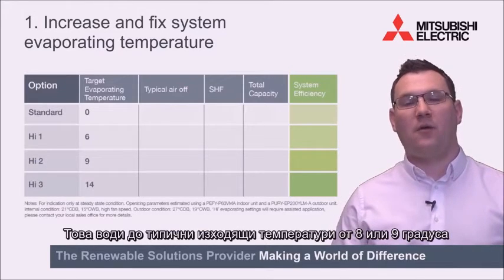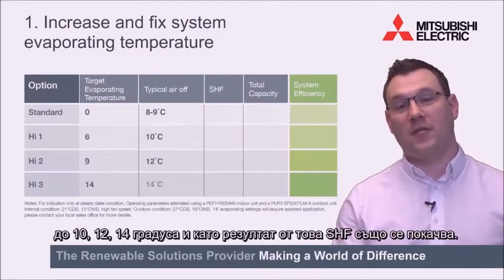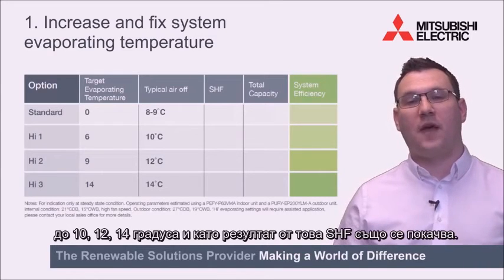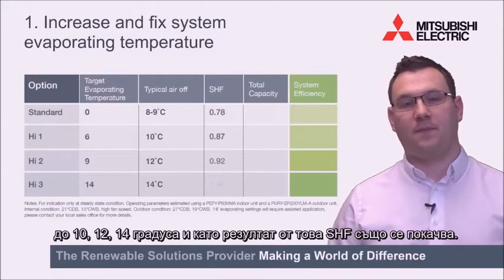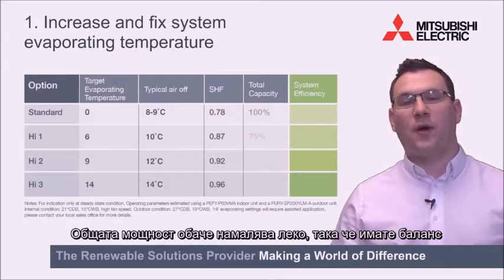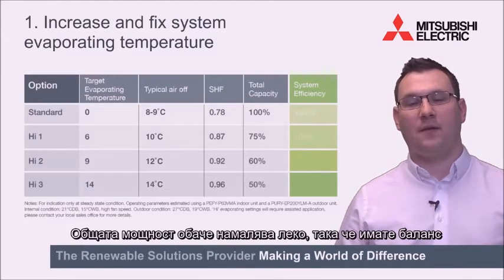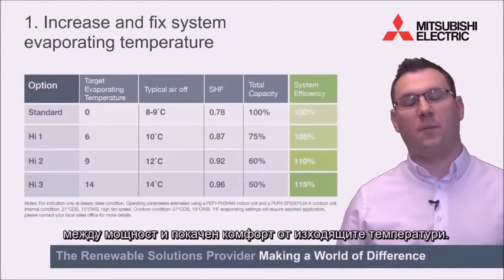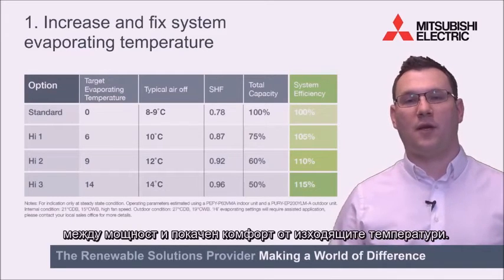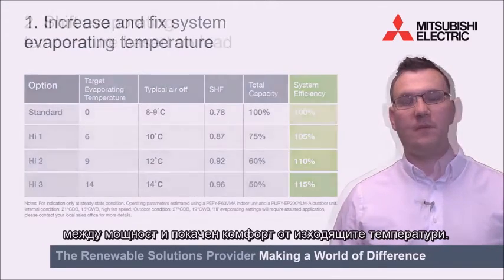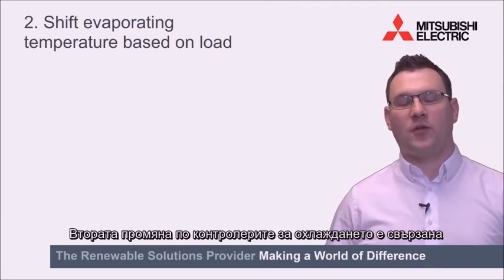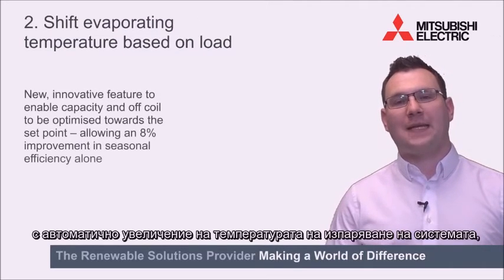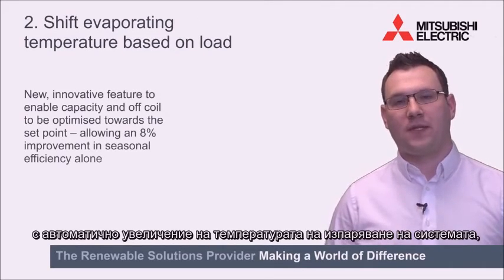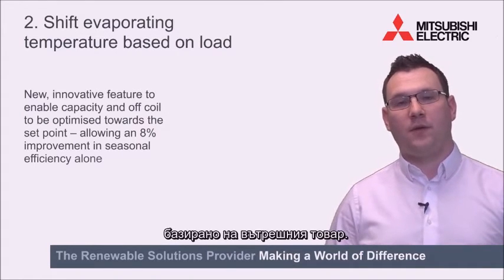This gives typical air off temperatures from the indoor units from your 8 or 9 degrees Celsius through 10, 12, 14 degrees. And as a function of that, the SHF also increases. The total capacity, however, does decrease slightly, so you're looking at the balance between capacity and increased comfort from air off temperature. The second of the cooling control function changes is around automatically increasing the evaporating temperature of the system based on the internal load.